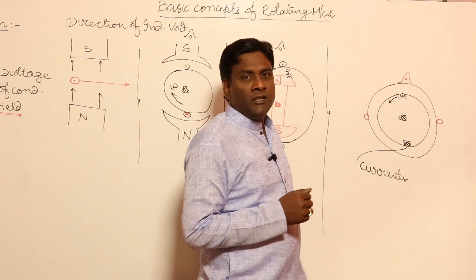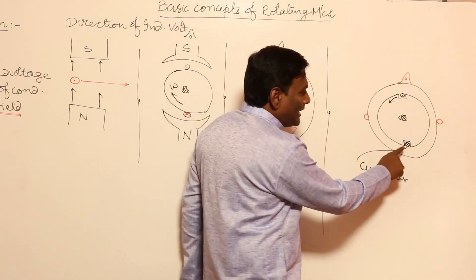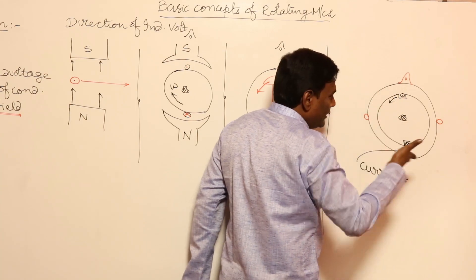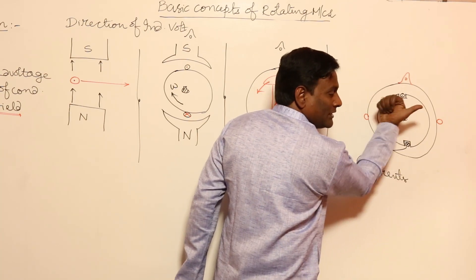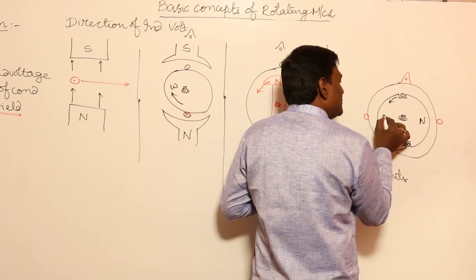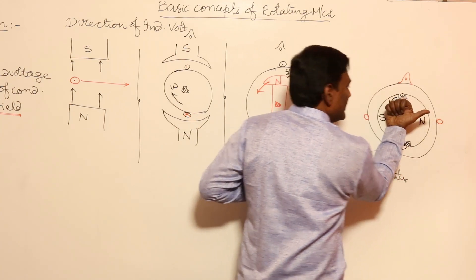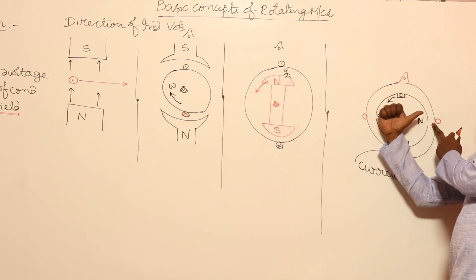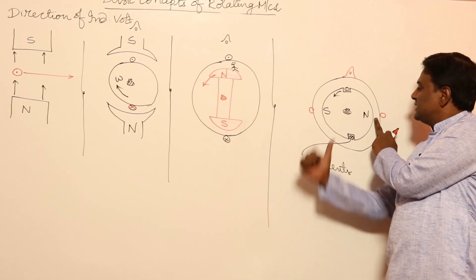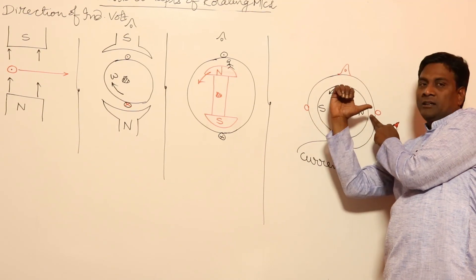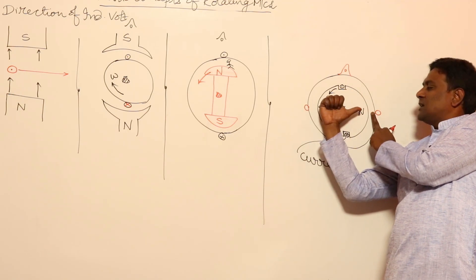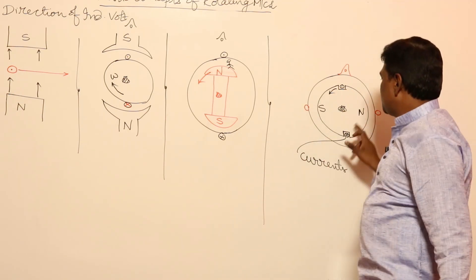Currents in the sense flux — whenever you have current, automatically flux should come. My currents are going to be cross here and dot here. So current enters here and comes out here, meaning flux will be in this direction. Now, if I sit in the air gap — flux is coming out of the rotor — so this should be N pole. Because flux is coming out of the rotor towards you when sitting in the air gap, this is N pole, and the other side is S pole.